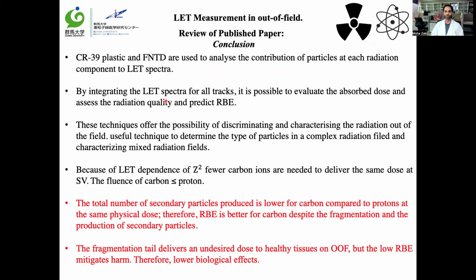By integrating the LET spectra for all tracks, it is possible to evaluate the absorbed dose, assess the radiation quality and predict RBE. These techniques offer the possibility of discriminating and characterizing the radiation out of the field. They are useful techniques to determine the type of particle in a complex radiation field and characterize a mixed radiation field.